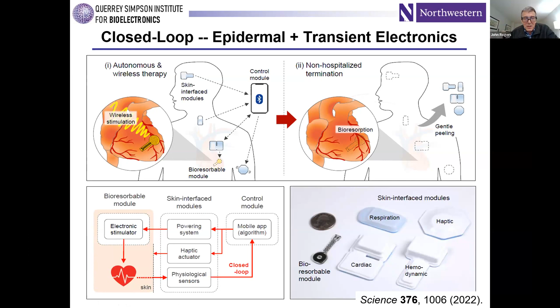And so you can embed all of that functionality into these skin interface patches that I was describing before that were designed to measure ECG, SCG, and PPG. Here we have a chest unit that's capturing ECG waveforms, but it also has an inductive coil that can wirelessly communicate to the implanted bioresorbable pacemaker so that the entire system can run autonomously in a closed loop manner without any wire-based tethers to constrain movements of the patients. This is what the electronics look like in that particular patch. We still have the analog front end and the ability to do ECG recording, but we also now have a source of RF power and a matching circuit to resonantly couple RF energy from this device to the implanted pacemaker.